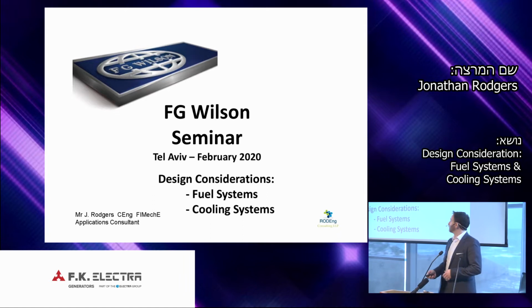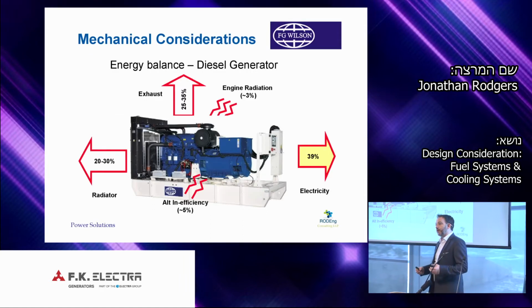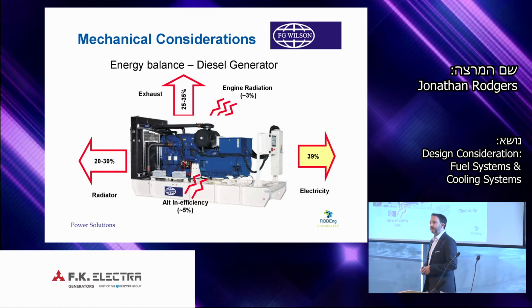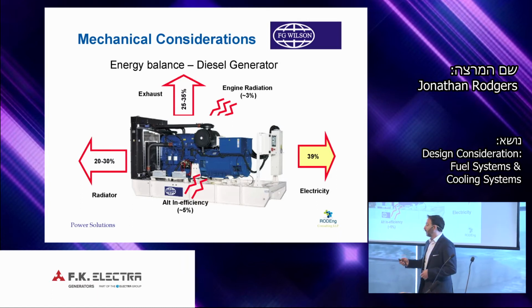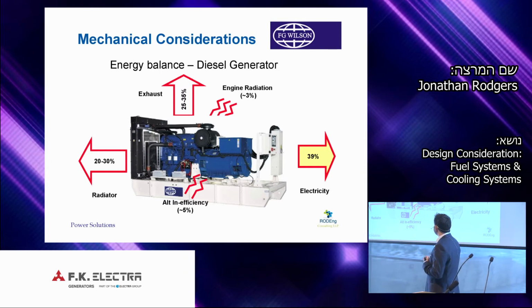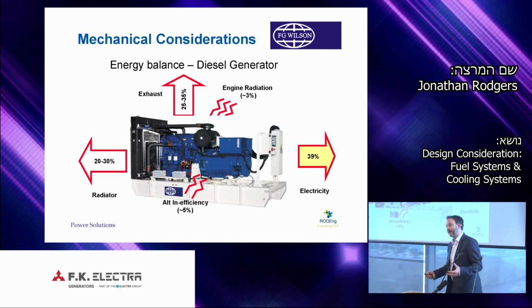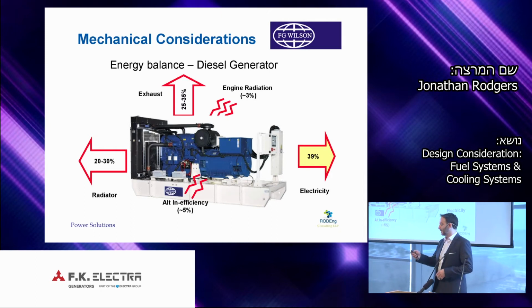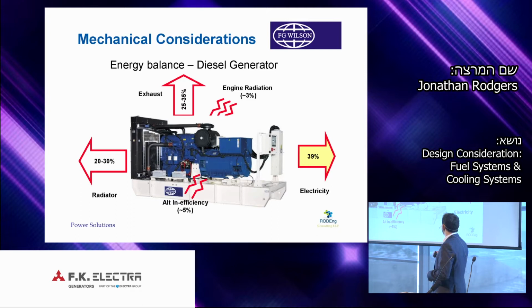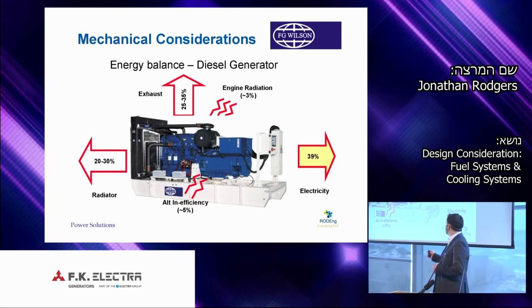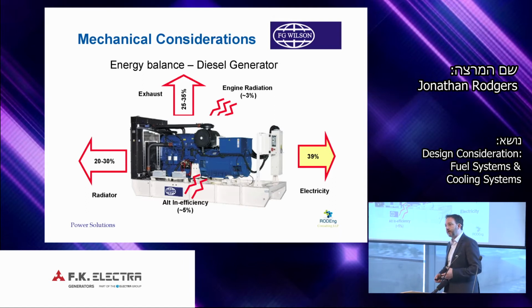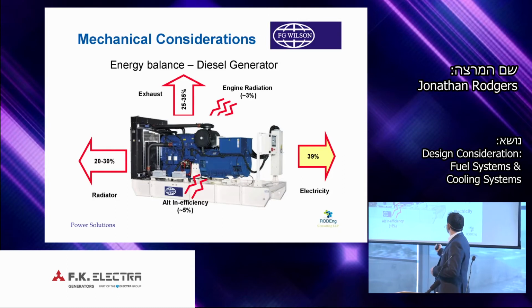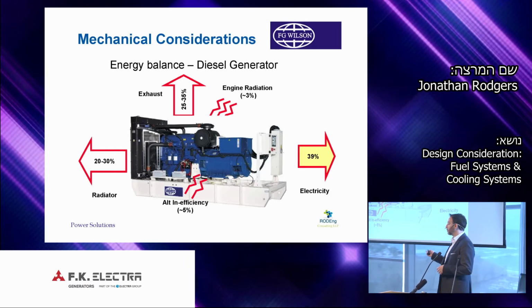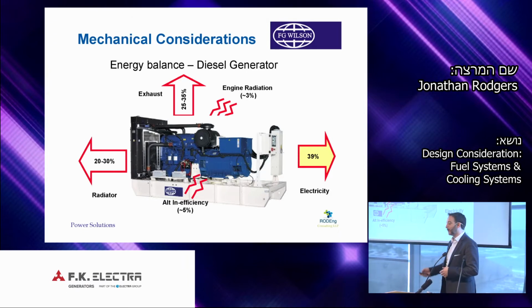What I'm going to speak about today are the mechanical considerations for generator applications. So my mechanical background, I deal with the energy that is in the system, in the energy balance, all of the mechanical aspect that is related to the output of electrical energy. So typically with diesel, high compression diesel engines, we're around 39 to 40% efficiency. So from fuel input, we'll have approximately 39% electrical kilowatt energy.